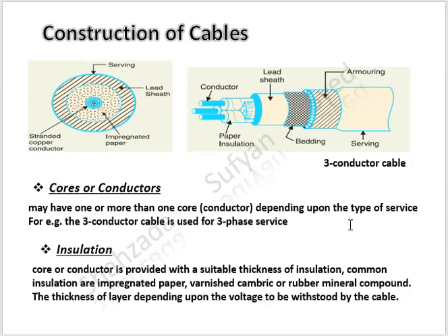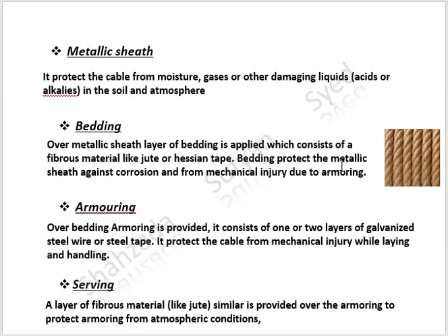The core or conductor is provided with a suitable thickness of insulation. Common insulations are impregnated paper, varnished cambric, or rubber mineral compound. The thickness of the insulation layer depends upon the voltage to be withstood by the cable — for higher voltage, the thickness of insulation will be high, and for lower voltage, less insulation is needed. The metallic sheath protects the cable from moisture, gases, or other damaging liquids such as acids and alkalis which are present in the soil and atmosphere.